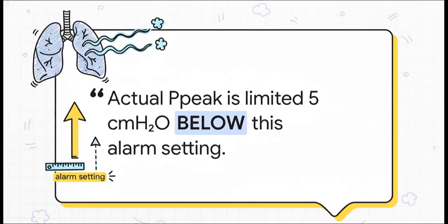Now, this is an absolutely critical point about the peak pressure alarm. You need to set it high enough to give the patient room for spontaneous sigh breaths, which are a totally natural, healthy part of breathing. The machine will limit the actual peak pressure to 5 centimeters of water below whatever you set this alarm to, so giving that extra headroom prevents a ton of nuisance alarms.